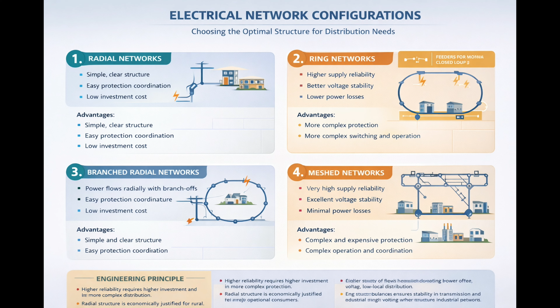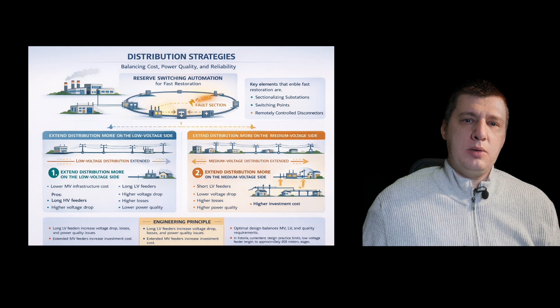Closed network schemes and ring structures allow supply reservation. In those systems, reserve switching automation is used. This automation restores power to the region without waiting for repair crews. Key elements that enable fast restoration are sectionalizing substations, switching points, remotely controlled disconnectors. These elements allow you to isolate the faulty section and re-energize healthy sections quickly.